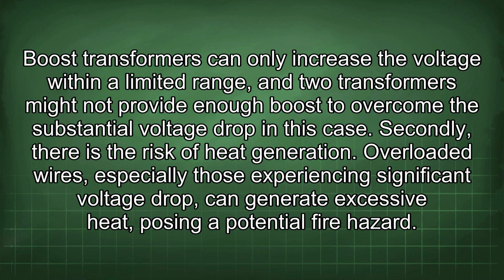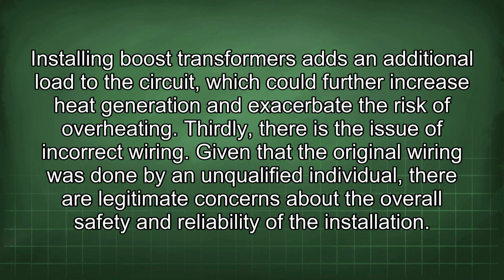Secondly, there is the risk of heat generation. Overloaded wires, especially those experiencing significant voltage drop, can generate excessive heat, posing a potential fire hazard. Installing boost transformers adds an additional load to the circuit, which could further increase heat generation and exacerbate the risk of overheating. Thirdly, there is the issue of incorrect wiring.